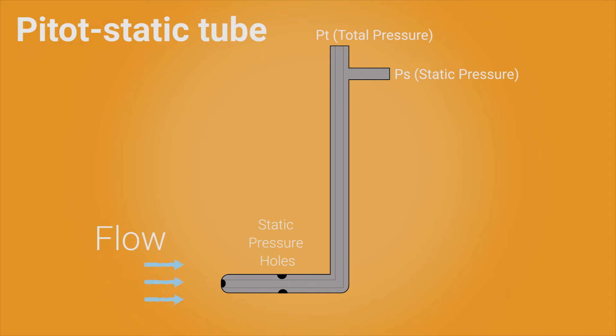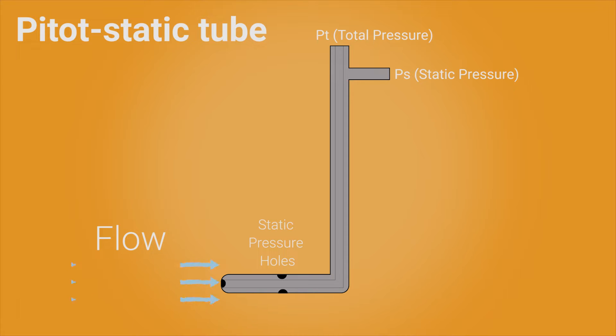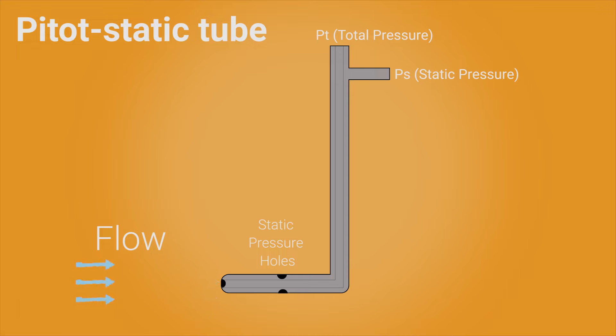How do we measure these pressures? We're going to be using something called a pitot tube, which encompasses a specific class of instruments that measure fluid pressures, and there are three basic types. You have the pitot tube, which measures total pressure; the static tube, which measures static pressure; and the pitot-static tube, which measures simultaneously the total and the static pressure in moving fluids.